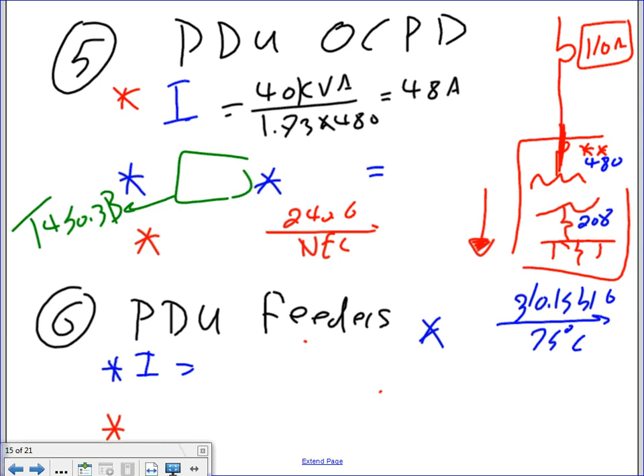Now, Adam, the PDU has a transformer. Can you guys see that there is a transformer right here? There is a transformer inside it. Unlike the UPS, there is a transformer for the most part. So when I size it, I'm going to size it like a 450.3(B) transformer. When I size the overcurrent protection device, I'm going to use 2.5. Why 2.5? Because there is a transformer inside that panel. It has a transformer, maximum. Okay, so 2.5 times 48, and that will get me 120 amp.